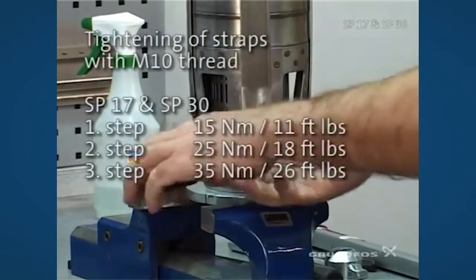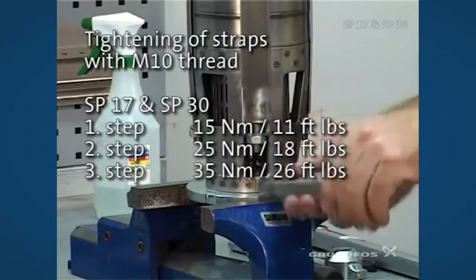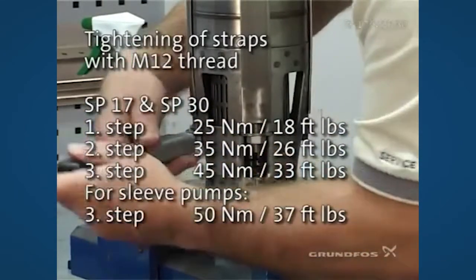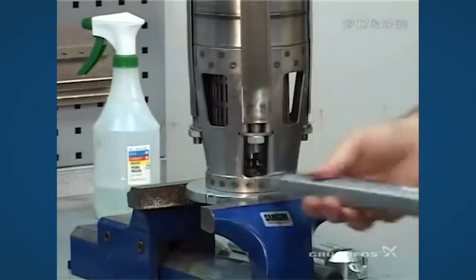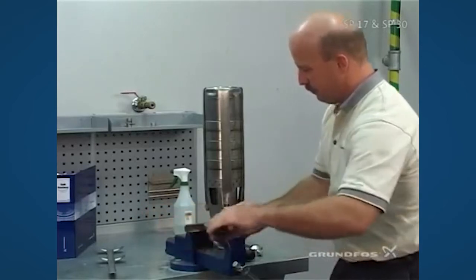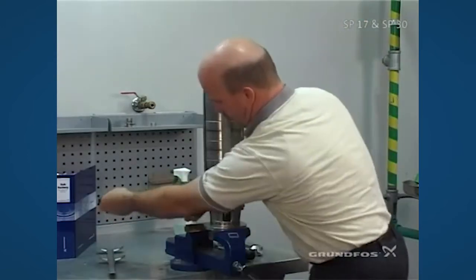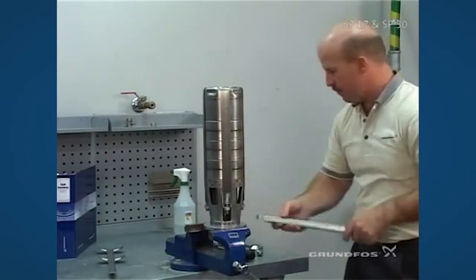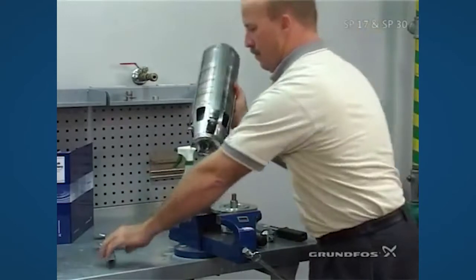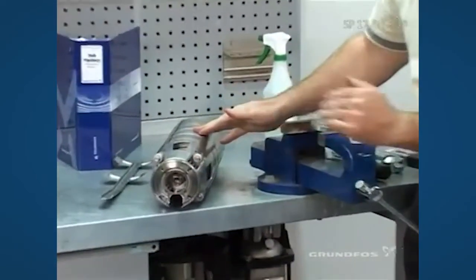Then take a torque wrench to do the first step of tightening. Make sure that you do it evenly to both sides. Go ahead and tighten it up with the torque wrench. Now the pump is completely built and we can take it loose. At this point we're going to want to check our end play, which is the travel in and out of the coupling.